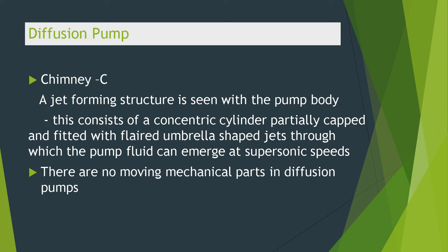A jet-forming structure is seen within the pump body. This consists of concentric cylinders, partially capped and fitted with flared umbrella-shaped jets, through which the pump fluid can emerge at supersonic speeds. This is the chimney, represented in the figure as C. There are no moving mechanical parts in the diffusion pump.